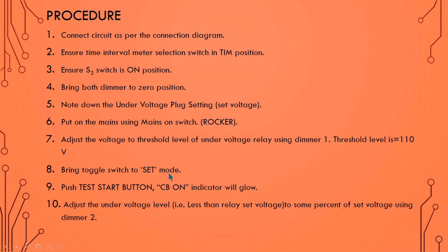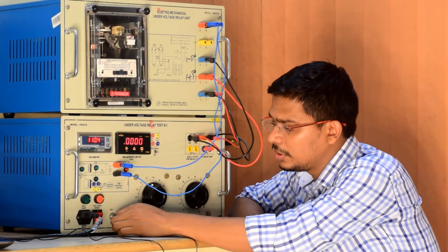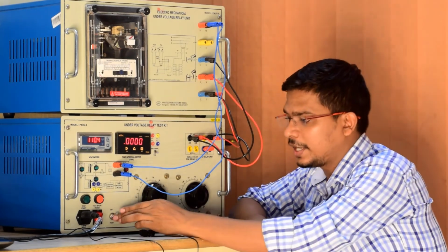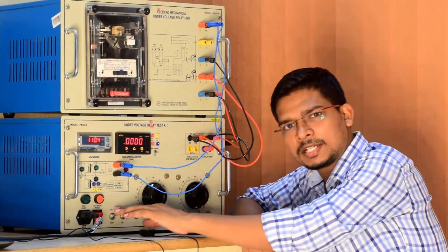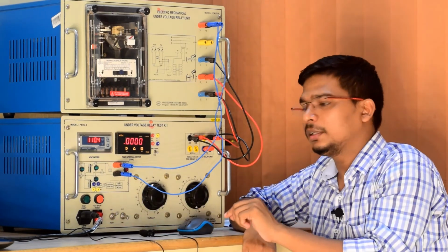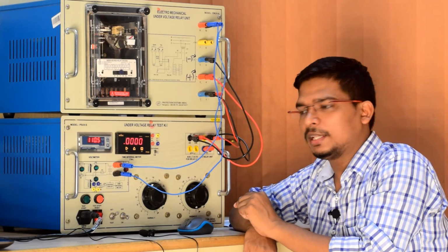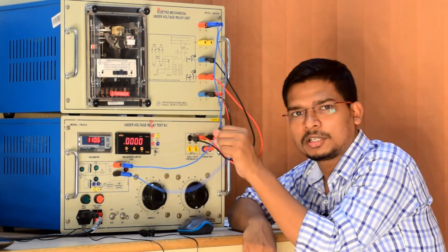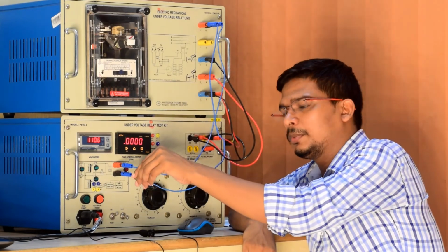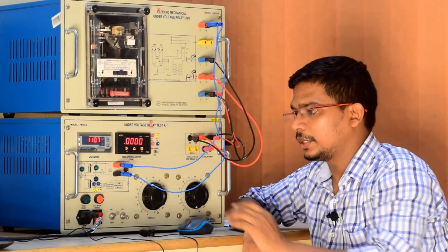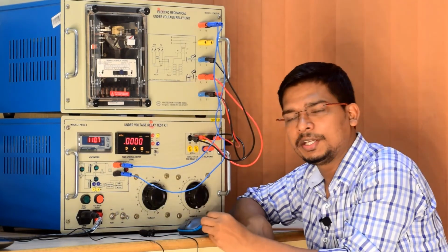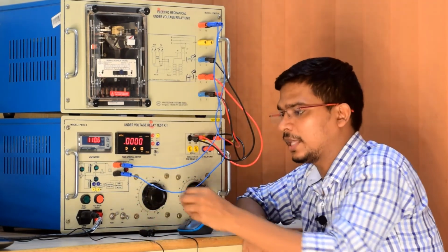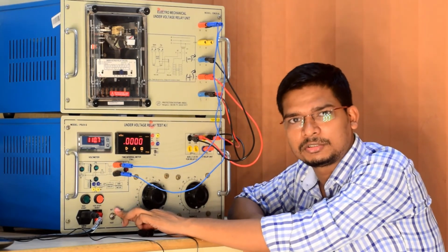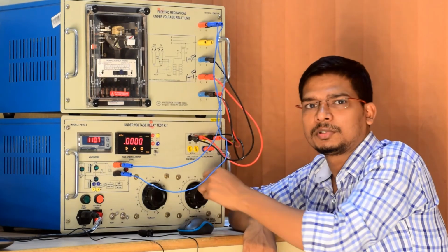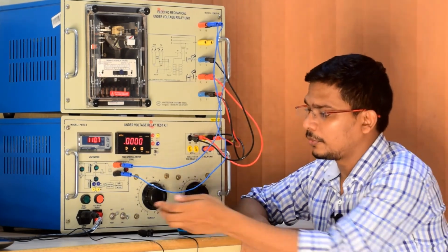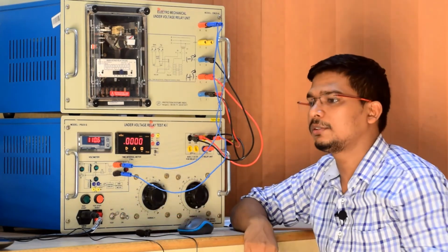Bring toggle switch to set mode. This is the toggle switch. This switch we have to make to set mode. Set mode means we have to set the voltage. As I told you, whenever the relay gets the trip signal, that trip signal will come to the circuit breaker, then the circuit breaker will trip the circuit, so that voltage will not go to the relay. But if this is in set mode, if the relay gives any trip signal, that will not come to the circuit breaker, that will be bypassed using this set and test switch. So this is the heart of this mechanism. So now this is in set mode. Next we will see the process.